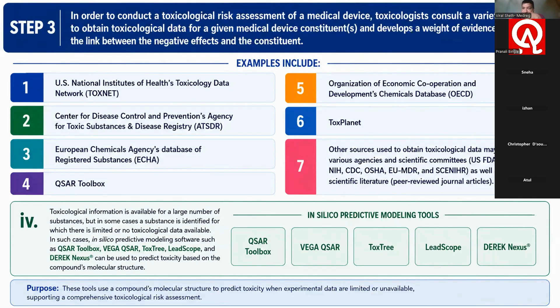After doing all this assessment, the toxicologist, as part 17 asks, mainly ensures the margin of safety, that is MOS, of your device. What is chemically extracted and leached must be within the margin of safety, depending on the total tolerable intake or contact limit, that is TI or TCL. TI is quantitative whereas TCL is based on surface area, depending on the nature of your device. The margin of safety of your device must be greater than 1. If it is less than 1, then a detailed study is required to identify the biological safety of your device.